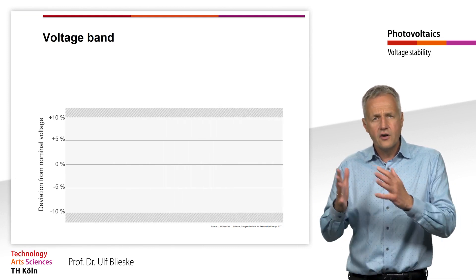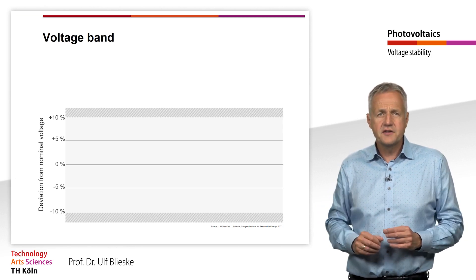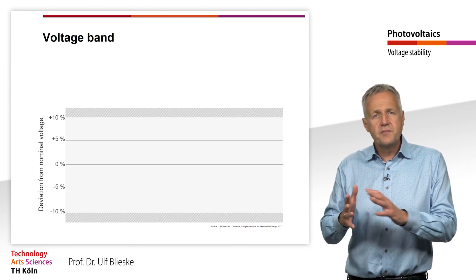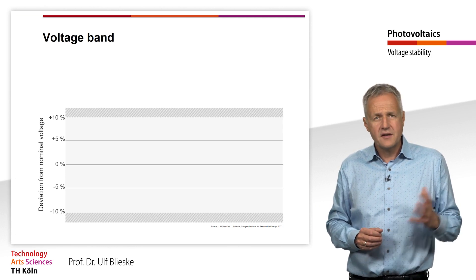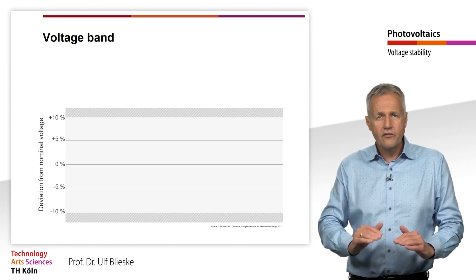Since the voltages of the low and medium voltage grids are rigidly coupled, the available voltage band of ±10% must be divided between the medium and the low voltage bands.